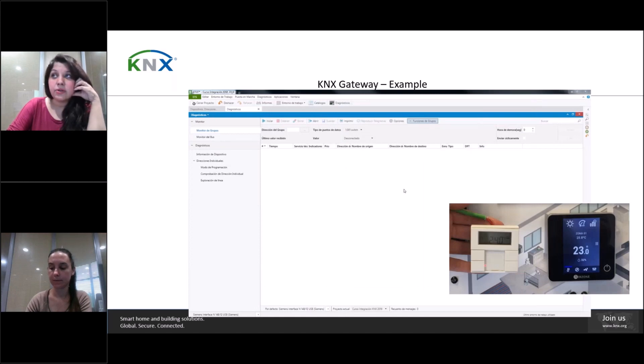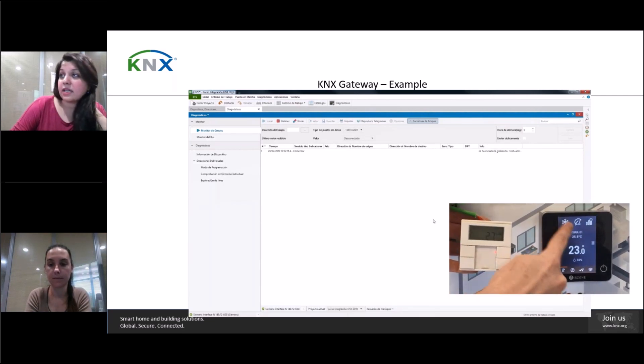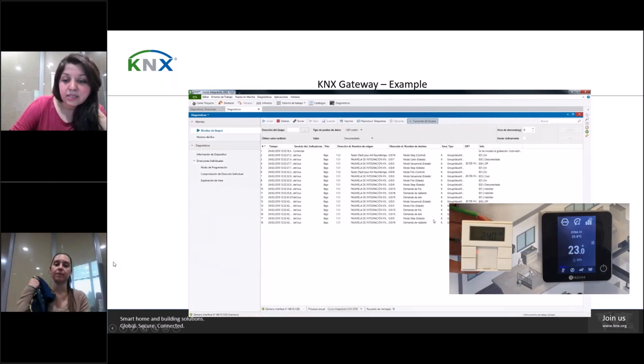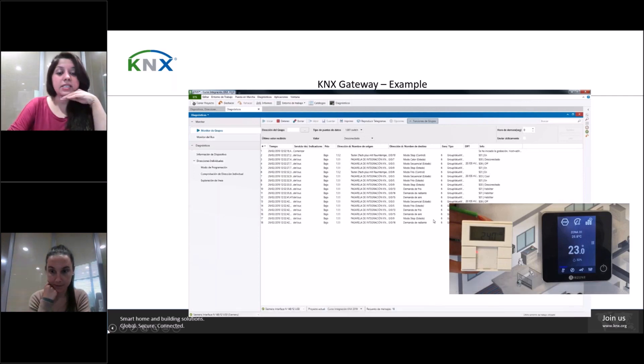Here is a small video showing simultaneously the KNX thermostat and our AirZone Blueface thermostat and the communication between them, along with what is happening in the ETS program behind the scenes. You can see the communication between KNX and AirZone, how demand is created, and what happens internally — the different parameters communicating via KNX. In the group monitor, you can basically see everything that's happening in real time.